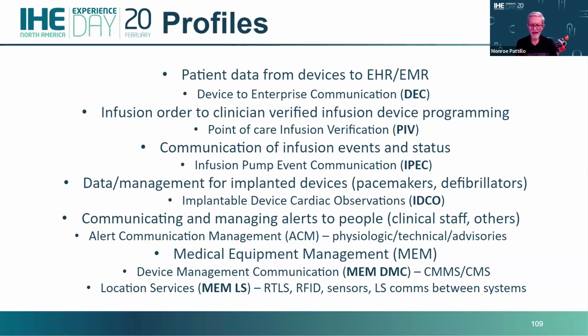You have systems that will manage the actual medical device, its battery status, its test status, its calibration and use status, and all of that information now has a profile, DMC, for device management communication. All of it started out as location tracking, RTLS, RFID, those kinds of things. But that mechanism has broadened into other forms of sensing. Like they found that if the tag has a temperature sensor in it, you can throw that in a refrigerator and monitor the status of your refrigeration or your freezing unit just by getting periodic data from the tag.